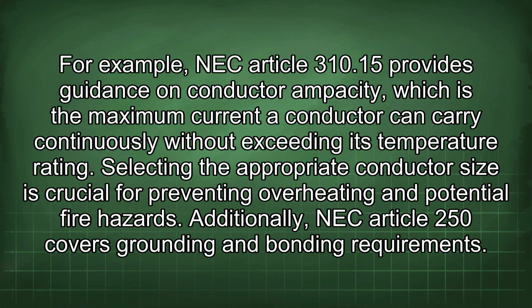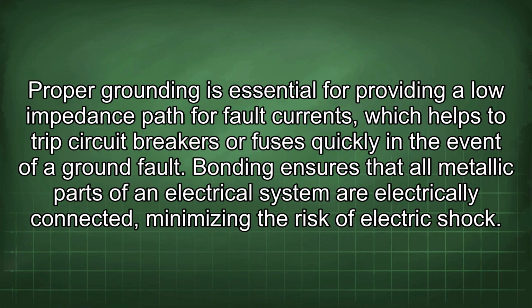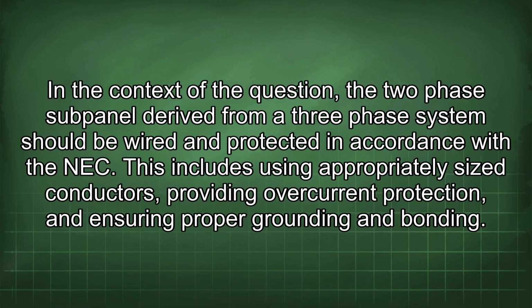Additionally, NEC Article 250 covers grounding and bonding requirements. Proper grounding is essential for providing a low impedance path for fault currents, which helps to trip circuit breakers or fuses quickly in the event of a ground fault. Bonding ensures that all metallic parts of an electrical system are electrically connected, minimizing the risk of electric shock. In the context of the question, the two-phase subpanel derived from a three-phase system should be wired and protected in accordance with the NEC. This includes using appropriately sized conductors, providing overcurrent protection, and ensuring proper grounding and bonding.